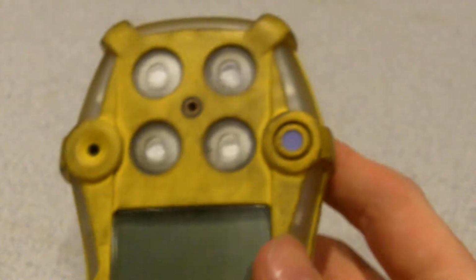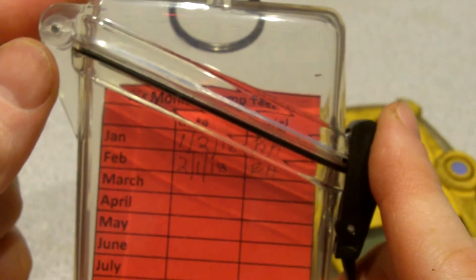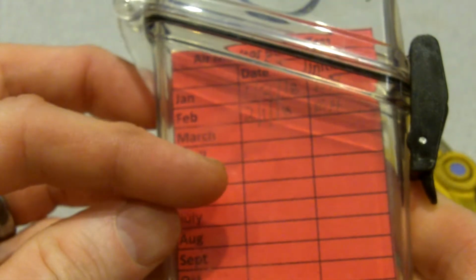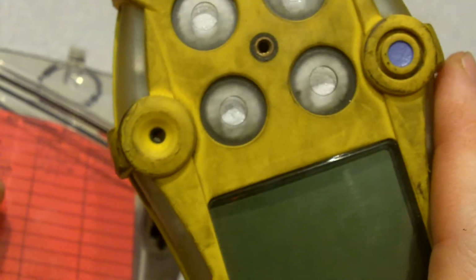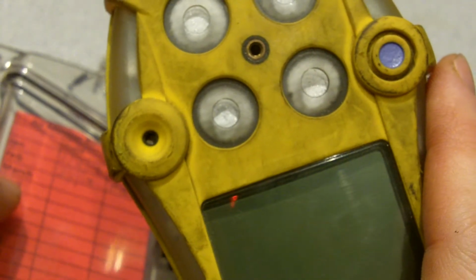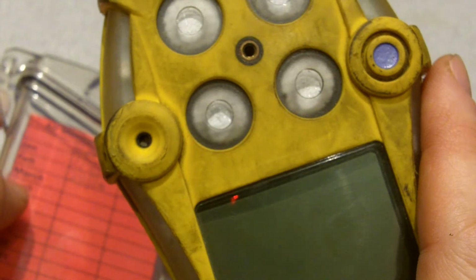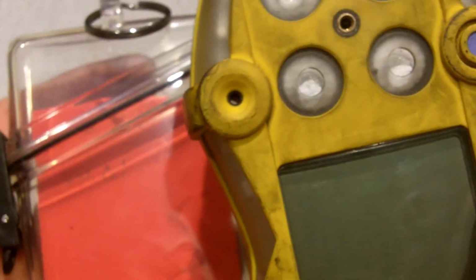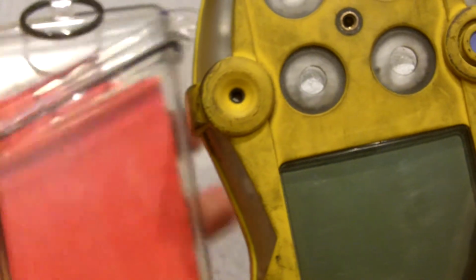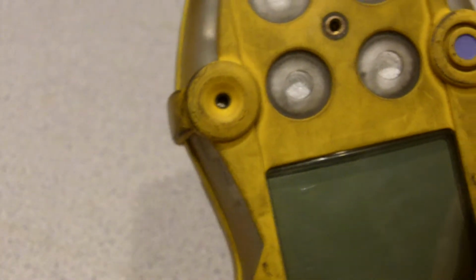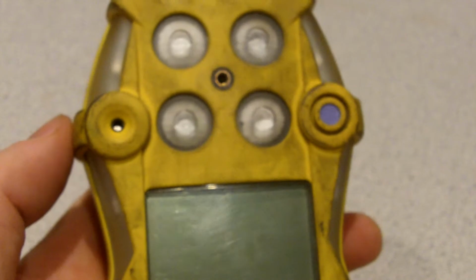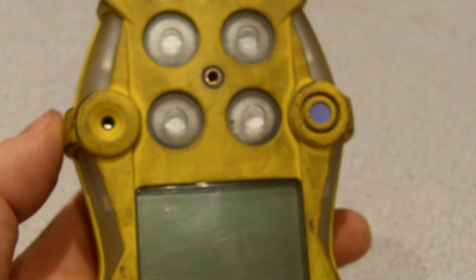Something also I'd recommend is having a log card. From here, we're able to see when it was last bump tested. A bump test is just exposing your gas monitor to gases and making sure that the alarm goes off. We do that every month. And then on the back of my card, I have a calibration log. It says every 180 days, I go through and set that to manufacturer's recommendations.